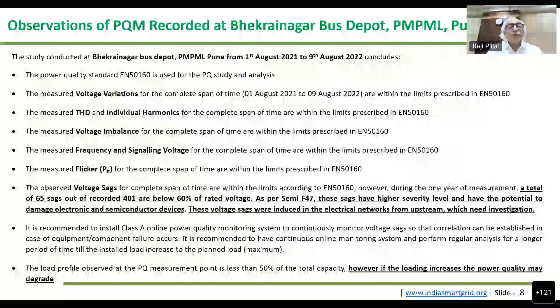But we also found voltage sags, which were happening very frequently. More than 400 voltage sags happened during this period, of which 65 sags were below 60% of the normal voltage. According to SEMI F47 standards, these sags below 60% have a very high severity level and have the potential to damage electronic and semiconductor devices in the nearby area connected to the grid. These voltage sags were actually induced into the distribution network from upstream, and typically we understand they come from the transmission grid, and this needs investigation.